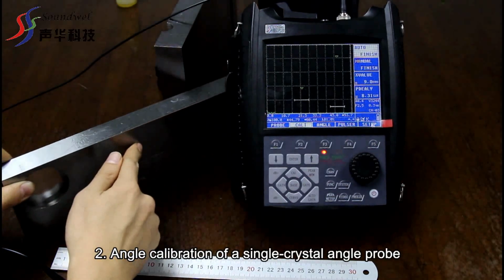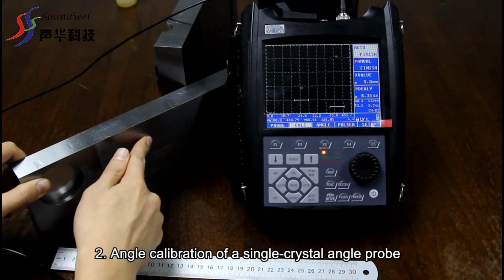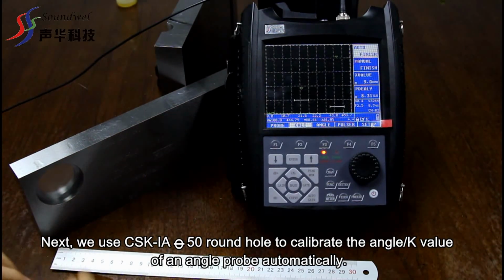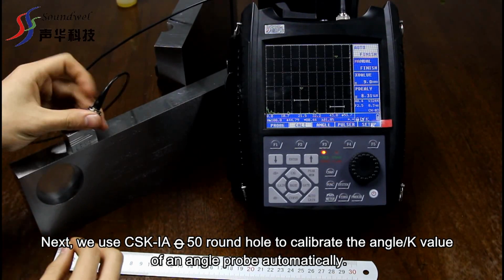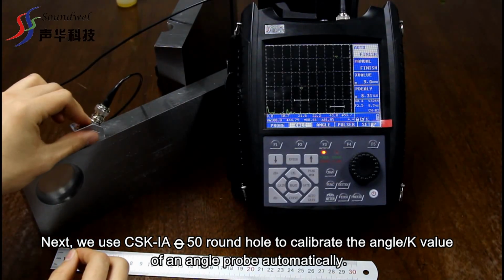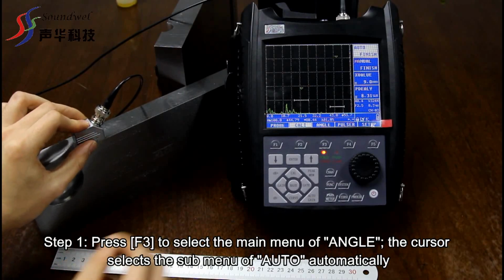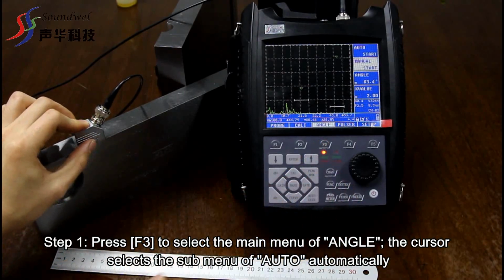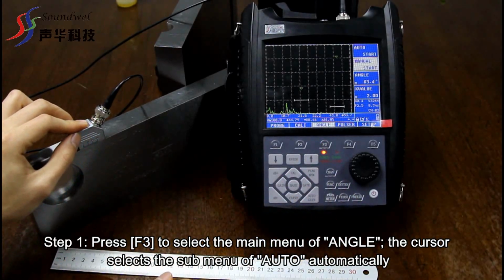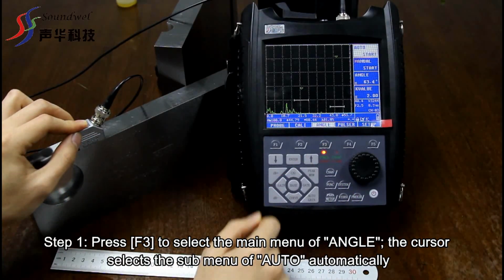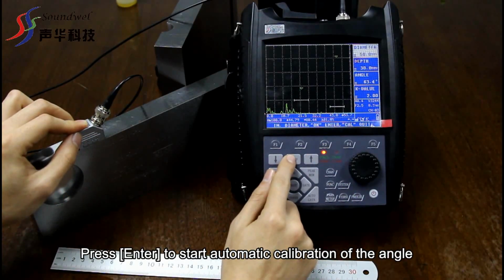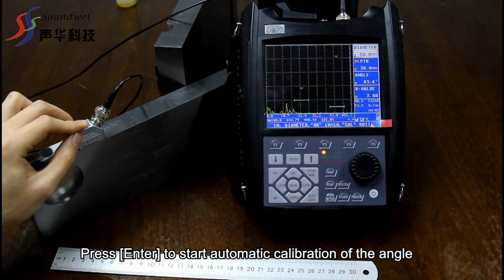2. Angle calibration of a single crystal angle probe. Next, we use CSK-IA 50 round hole to calibrate the angle K value of an angle probe automatically. Step 1. Press F3 to select the main menu of Angle. The cursor selects the submenu of Auto automatically. Press Enter to start automatic calibration of the angle.